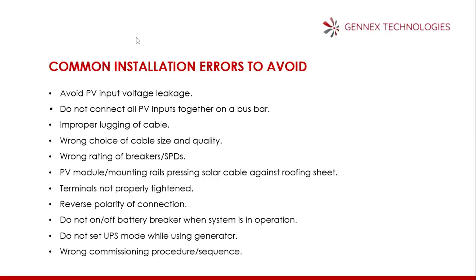PV module and mounting rails pressing the solar cable against the roof sheet is wrong. Absolutely wrong. This is going to give you solar leakage. Terminals not properly tightened can cause noise, burns, and can lead to fire outbreak. Reverse polarity of connection can instantly damage the inverter.